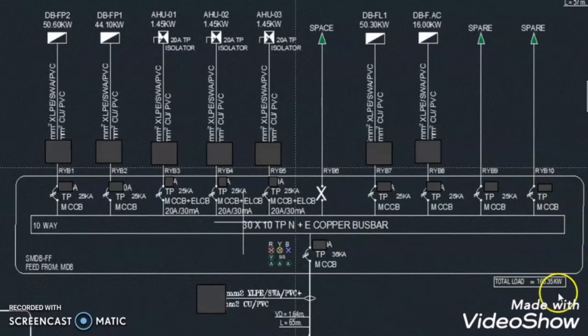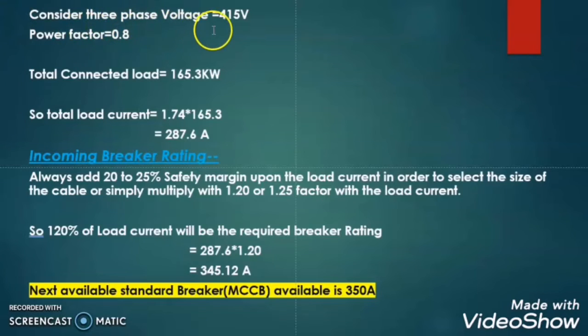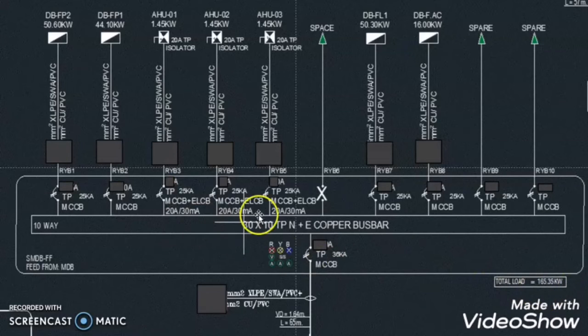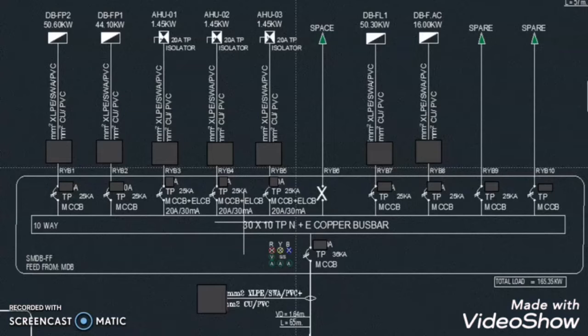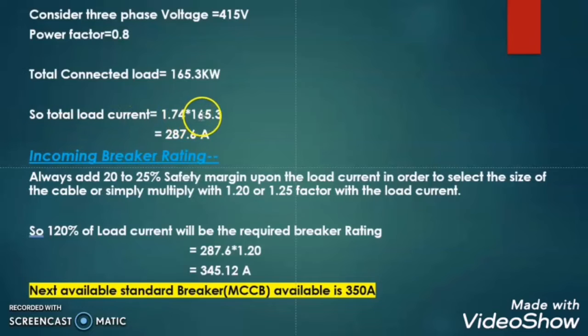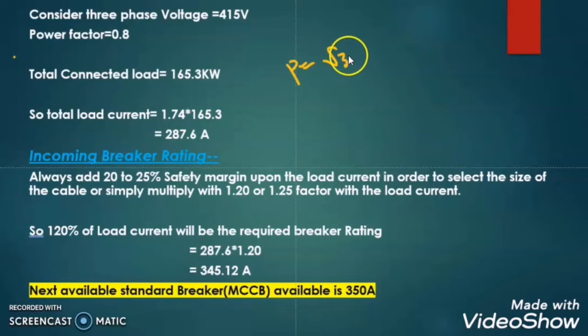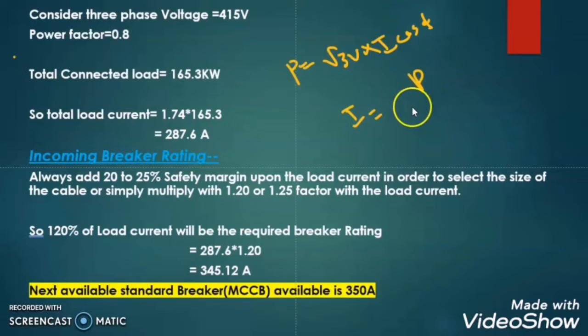Let us calculate first the main incomer breaker rating for this sub main distribution board. Here you can see that the total load connected is 165.35 kW. I consider that the 3-phase voltage is 415V and the power factor maintained is 0.8. The total connected load for this SMDB is 165.3 kW. So the total load current is 1.74 multiplied by the total connected load, that is 165.3. This is the shortcut method. If you want to go with the power formula, then P = √3 × V × I × cos φ, so I = P ÷ (√3 × V × cos φ).